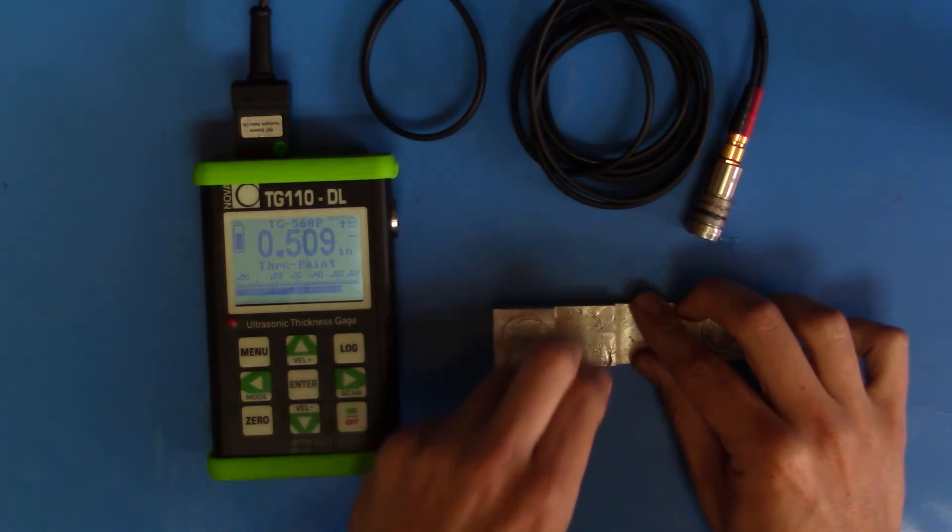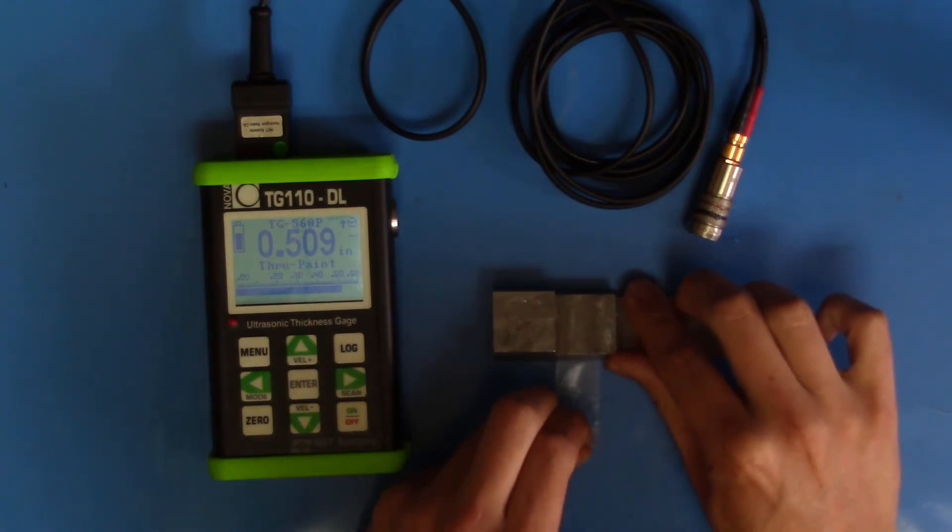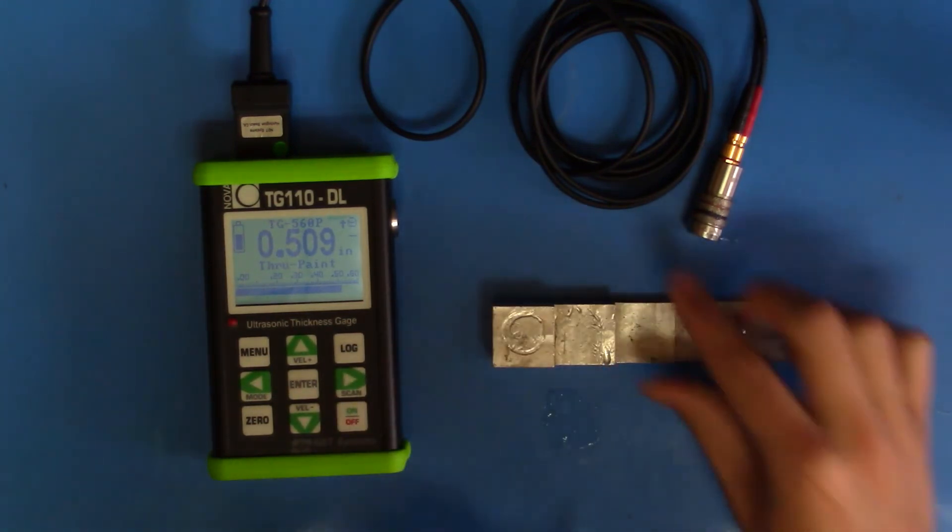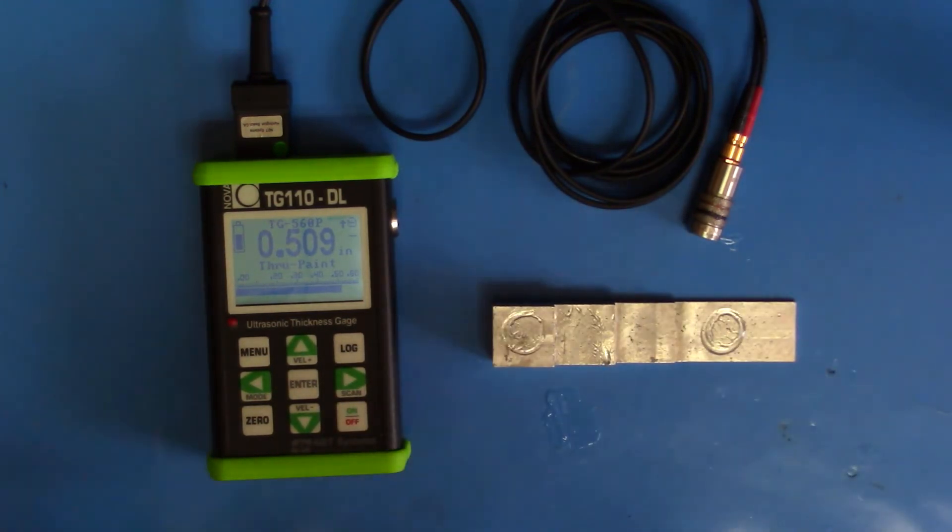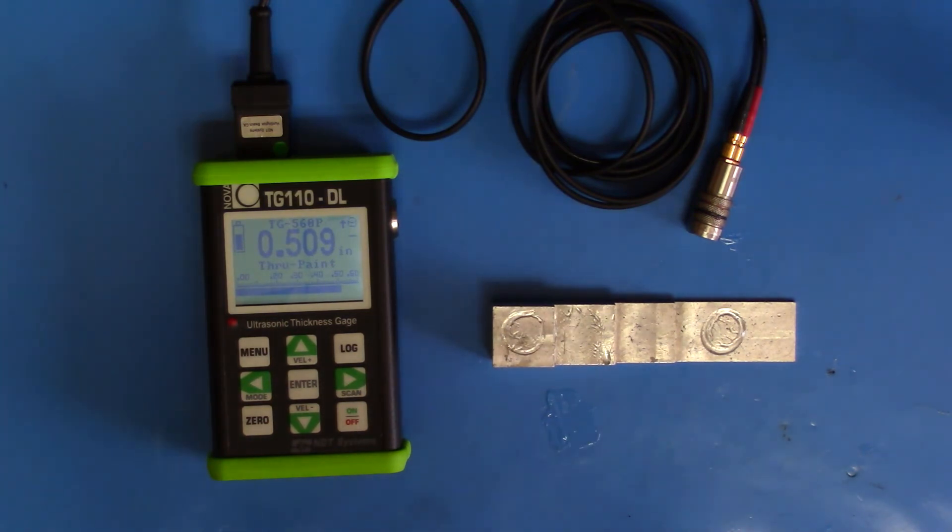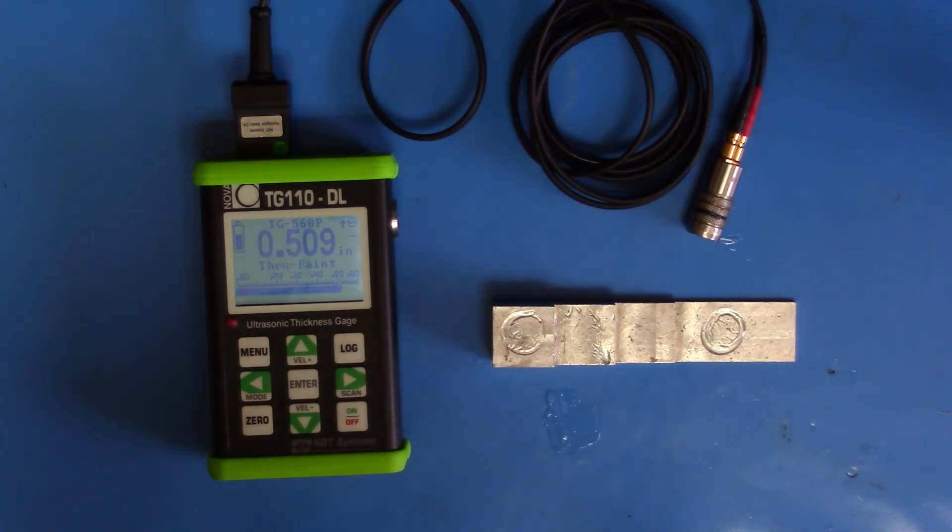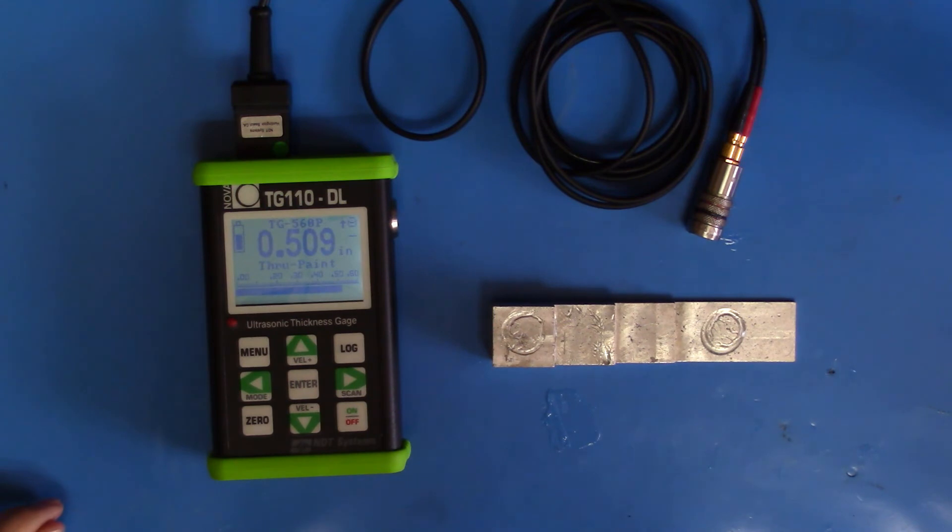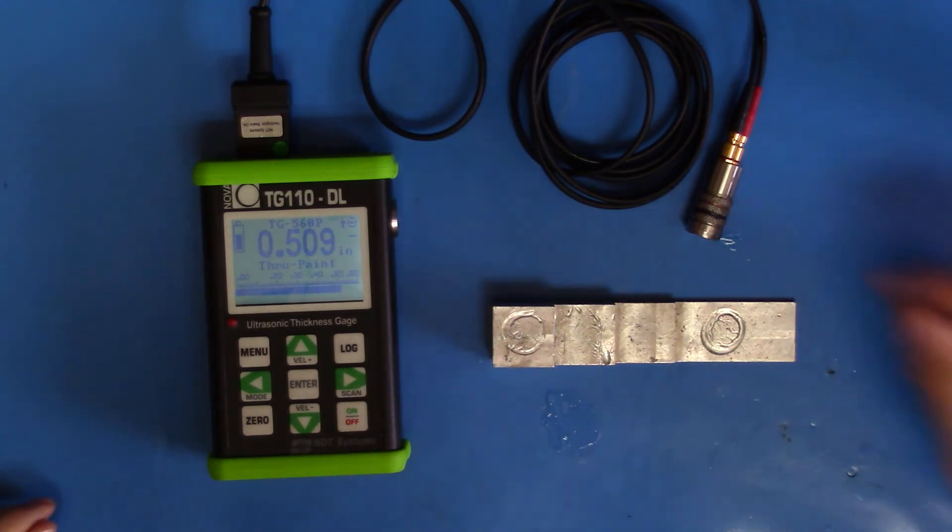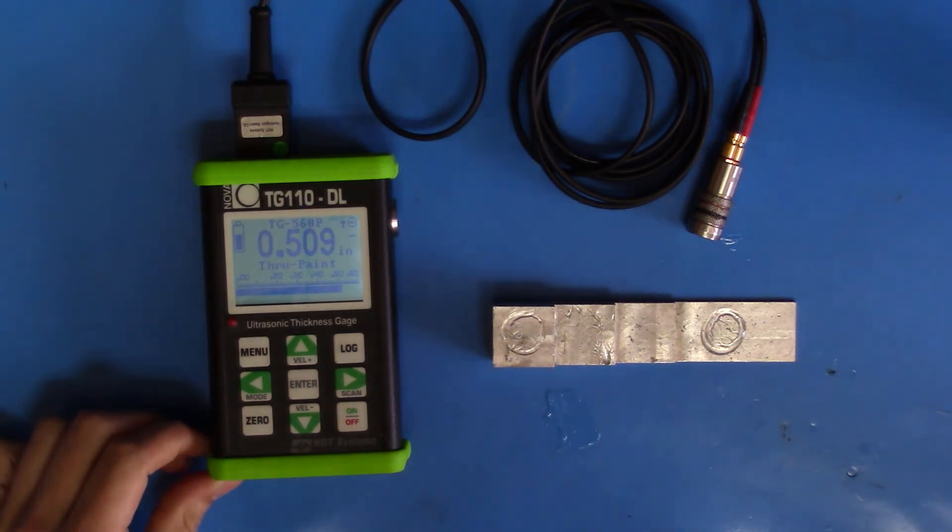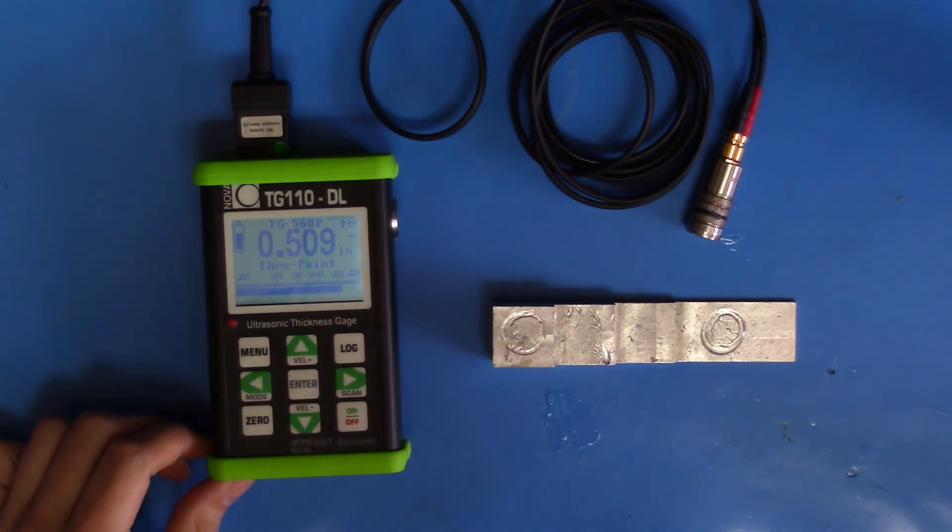Now, you want to use ThruPaint coating if you have a sample that you're trying to read, but you're not able to remove the coating. Say, if you have a tank with a weather-treated exterior coating. You don't want to remove that to keep the tank in good condition. With this, you can measure through it.